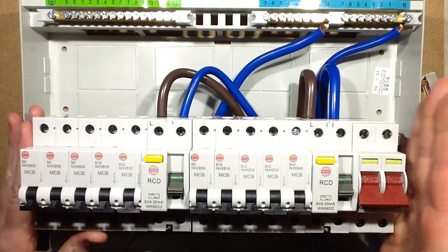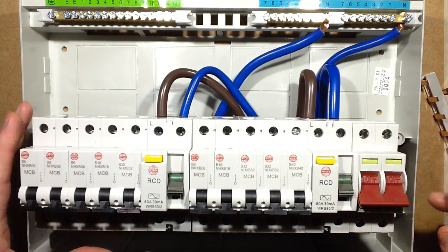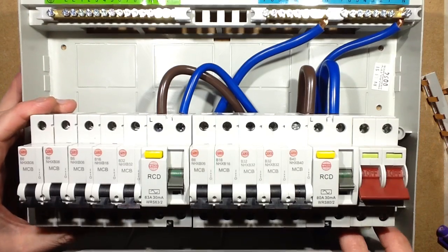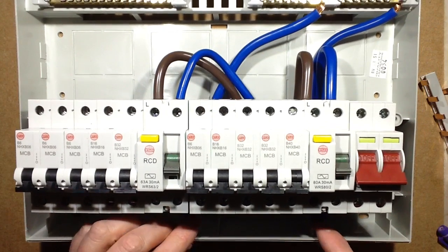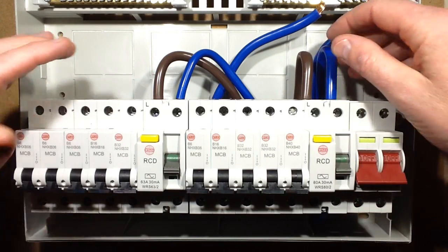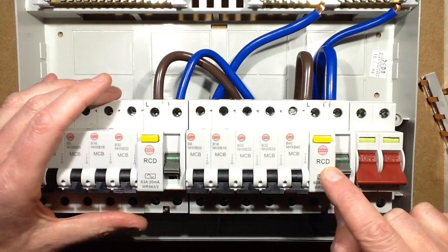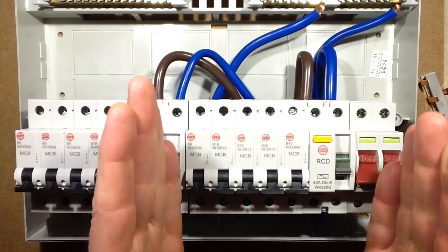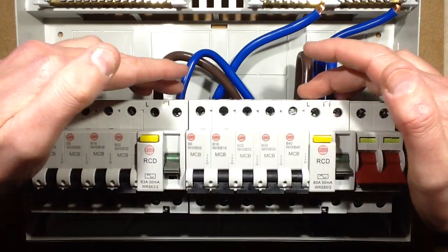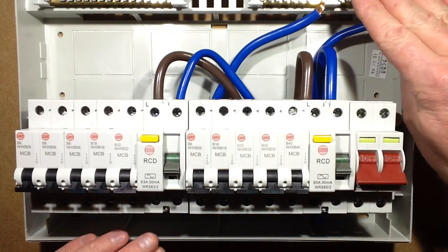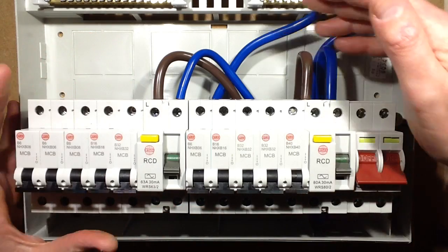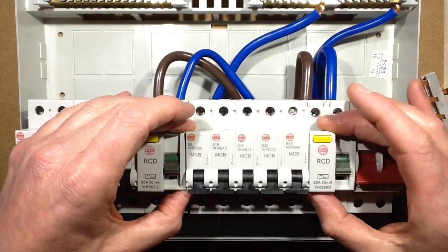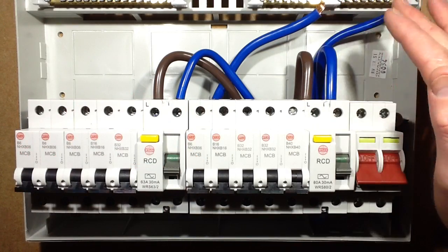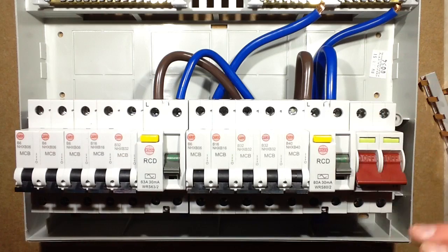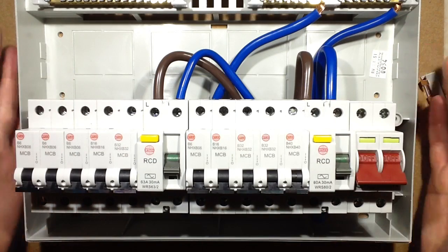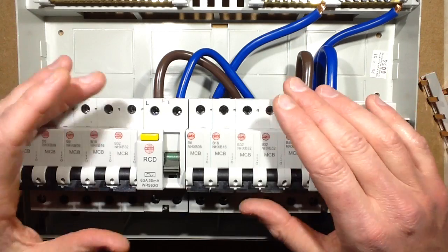I shouldn't refer to that as a breaker because it is an isolator, that's its correct name. And the power comes into that, live and neutral, and then comes out the bottom of it, and then feeds into a separate earth leakage breaker, an RCD, residual current device, or ground fault interrupter as it's known in some parts of the world, for each section of breakers. Each one has the neutral coming out, going to its own separate neutral bar, because you can't use one common neutral bar. Each RCD and its set of breakers has to have its own separate bar, and the neutrals can't be combined, because if they are, it will result in imbalance of the current going back through the breaker and cause false tripping.